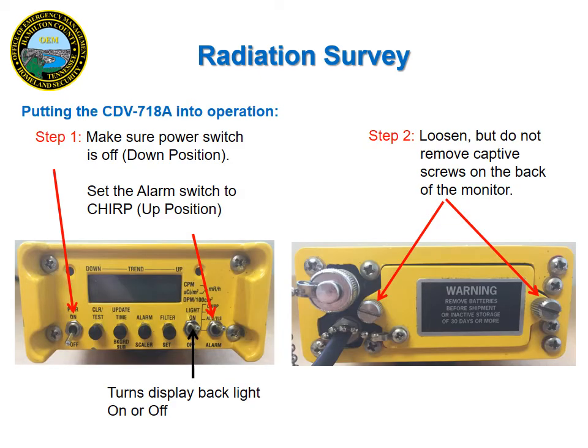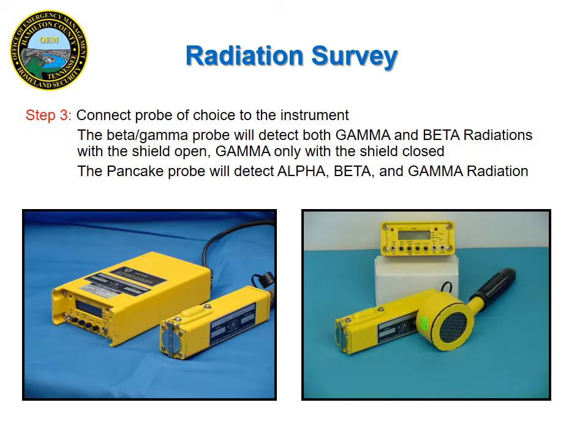So to get your 718 into operation, you must first make sure the power switch is off and the alarm switch is switched to chirp. This is so you can hear when the meter is actually going off. Then you will loosen the screws on the battery cap on the back of the meter. Next, you will connect the probe. In most cases, you'll be using the pancake probe, which will detect alpha, beta, and gamma radiation.